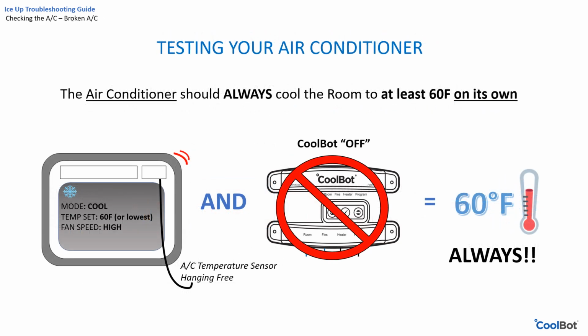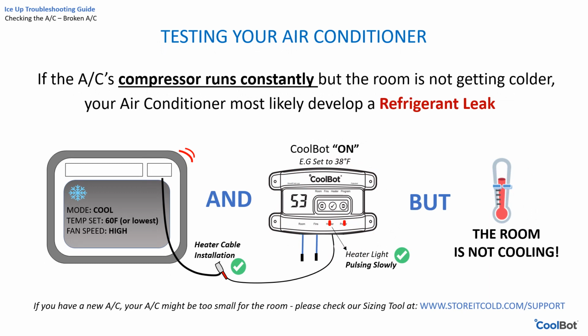If your air conditioner running on its own, without the CoolBot connected to the power supply, fails to maintain the room temperature at the air conditioner's lowest temperature setting of 60 Fahrenheit, or if the compressor is constantly running without cycling, but fails to cool the room anymore beyond a certain point, then there is a problem with the air conditioner unit. If this is a new install, then your air conditioner might be too small for the room. Check our website for the correct sizing of air conditioner for your room. If this is a cooler that has previously worked well with the CoolBot and started showing this problem, this means that your air conditioner developed a refrigerant leak and it has lost some of its cooling capability. The air conditioner needs to be replaced.